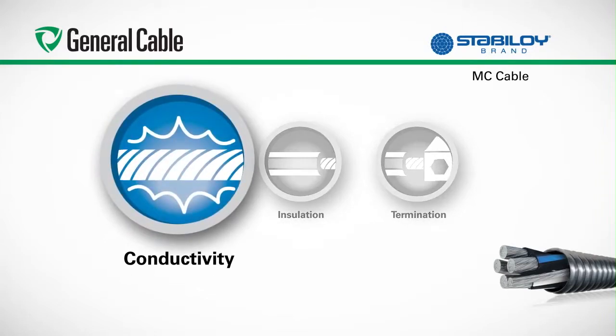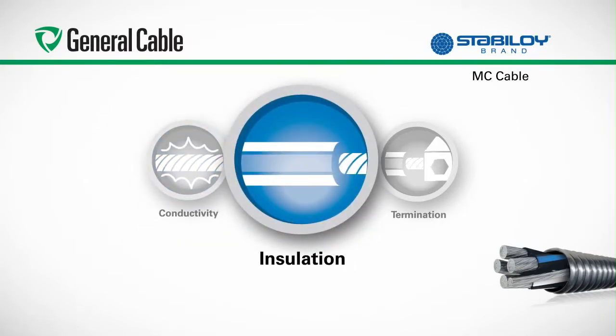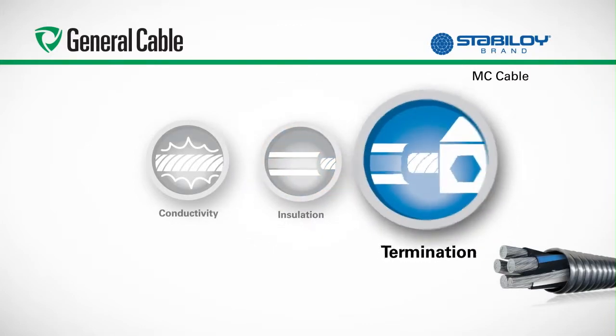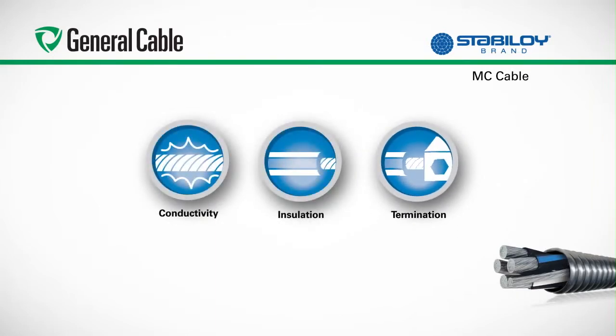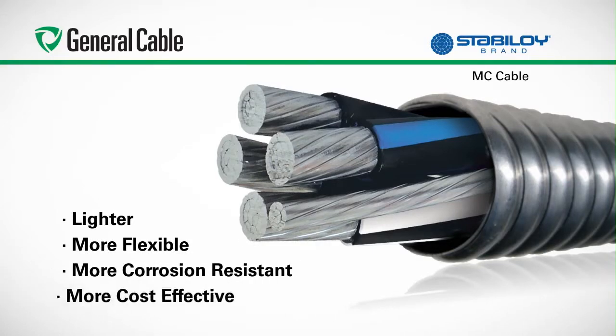In conductivity, aluminum conductors feature twice the ampacity per pound as equivalent copper conductors. In insulation, the cross-linked polyethylene on Stabiloy brand conductors performs better in every application, including cold impact, wet electrical, and long-term aging tests. In termination, Stabiloy brand aluminum alloy construction terminates safely with industry-standard dual-rated aluminum lugs. The similar metals connection means you get a safe and reliable termination. In addition, Stabiloy brand conductors are lighter, more flexible, more corrosion resistant, and much more cost-effective than copper conductors.